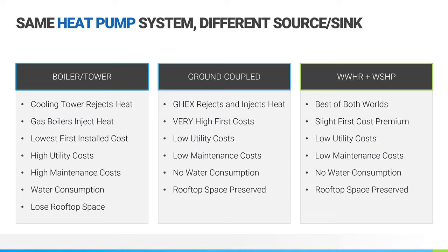One of the drawbacks to it is the increased utility costs and potential high maintenance costs associated with it because of the cooling tower and boiler maintenance. And again, going back to the rooftop venue, they would lose the rooftop space to the boiler room and cooling tower room on the top. So when they went to the ground coupled option, instead of having the cooling tower and boilers, you've got the underground heat exchanger that's rejecting and injecting the heat. There they were going to be incurring some very high first costs just associated with the amount of drilling that would be required. You would see lower utility costs, way lower maintenance costs. You would have no fresh water consumption and you would preserve your space, but it was that first cost for a municipal utility that they could not get over.